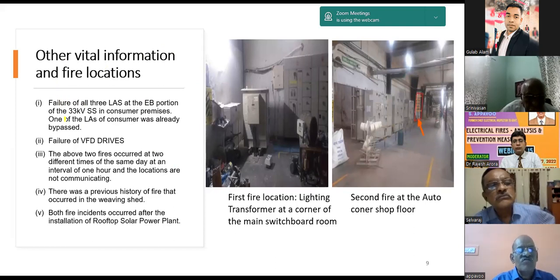Some other vital information I obtained during the visit was that there was a failure of all the 33 kV line substation lightning arresters and VFD drives. There was a failure of VFD drives in the auto coner machines. Normally, VFD drives, being power electronics, are susceptible to voltage spikes. During the power failure, as soon as the first fire occurred, these VFD drives also failed. Then we have to note that two fires occurred on the same day.